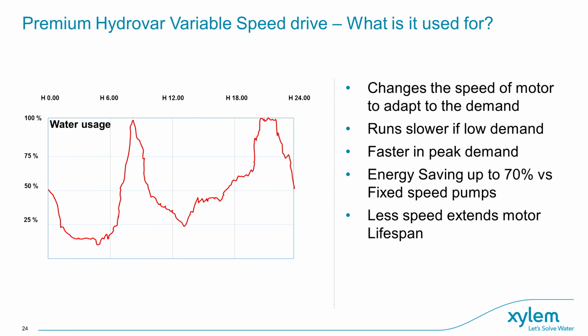The main purpose of a variable speed drive is to adapt the speed of the pump to suit the demand in the application. For a typical water boosting application, with a booster set being used for a block of flats, let's say, the demand is not constant throughout the day. You will get peaks of water usage in the morning, when the occupants first wake up, and in the evening when everyone returns home from work. However, during the middle of the day and at night, the water consumption is minimal.